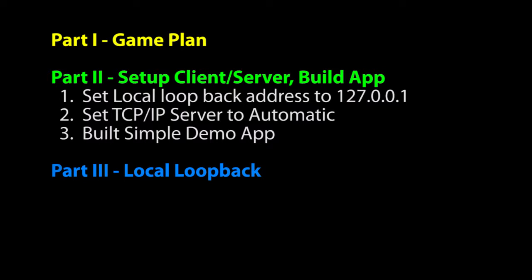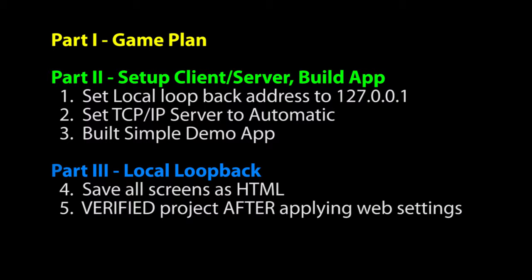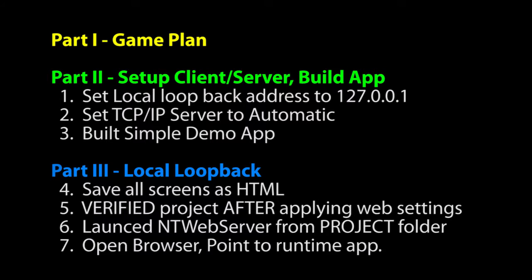In this video, we took that project and we saved all of the screens as HTML files that the client could download and use. We have verified the project after setting all the web settings. Remember, any time you make a web setting change, you have to re-verify the project to get the file associations to line up. We launched the NTwebserver from the project folder so we would have a little mini network running.